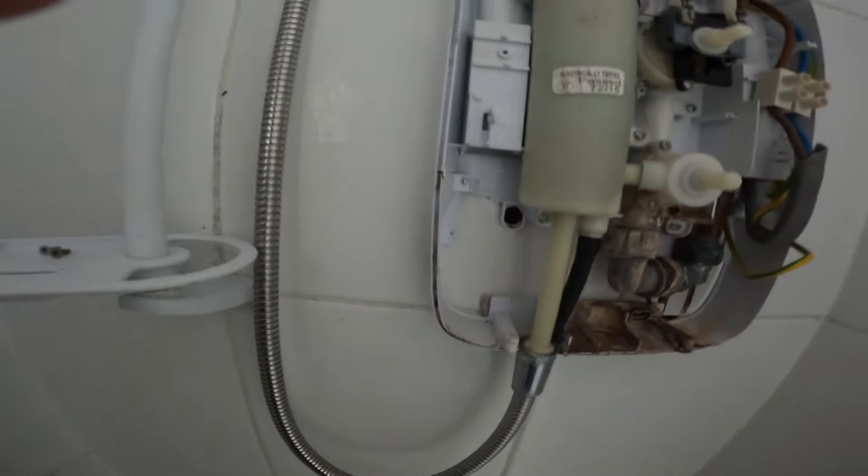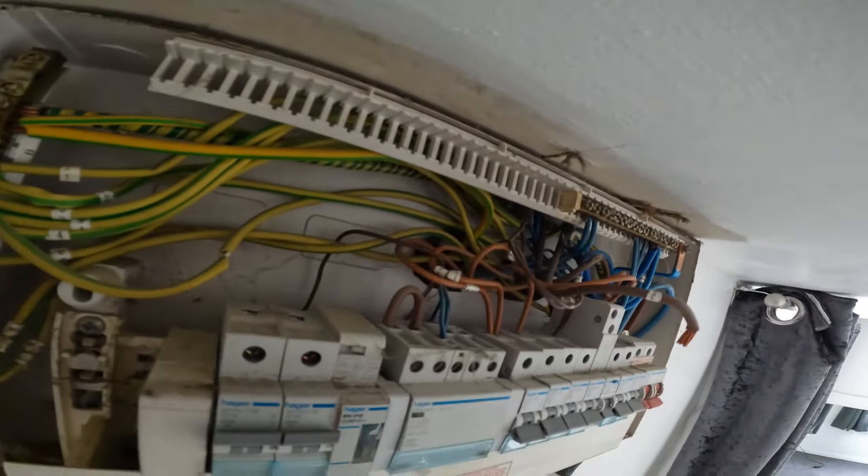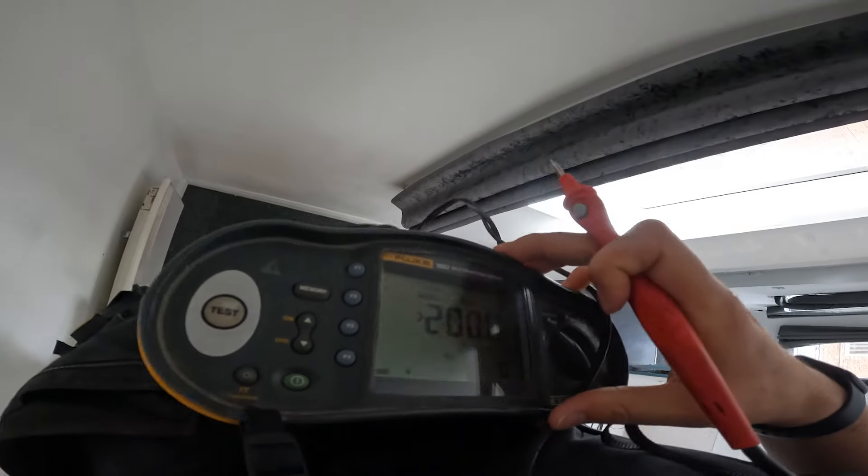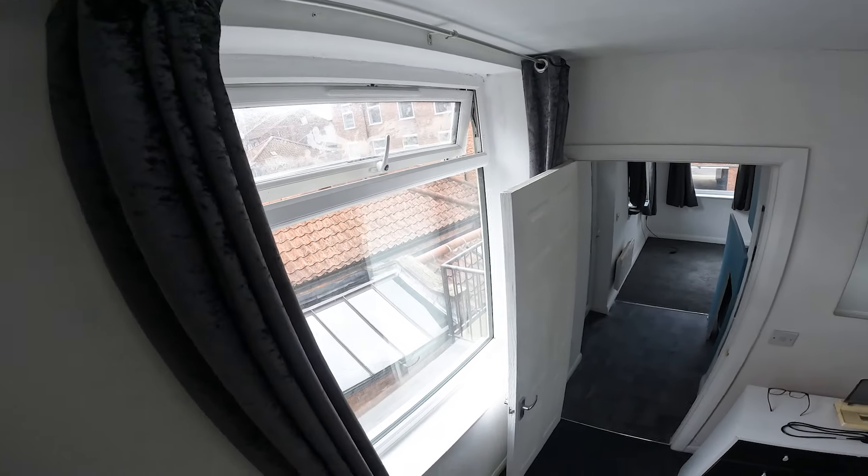We're testing the shower now - we've got to take the line cable out and connect that to earth. Going to the furthest point. We're getting 0.10 on continuity, so we're going to do an insulation resistance test as well. I'm just going to check that there are no IP issues. It's been swapped before and doesn't quite match up, but it's okay - it's sealed around. We also checked the isolation connections because bathroom pull cords - it's always like the tiny little screwdriver, never tight enough and it just sets on fire. The insulation resistance is getting 200 meg on the 250V test - that's passed.